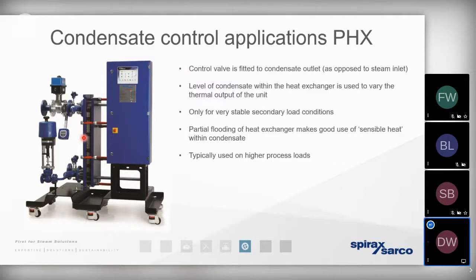The benefit being that regardless of the fall in pressure downstream of the steam trap, we're greatly minimizing, if not eliminating, any flash steam losses or flash steam inefficiencies. So we can actually move the control valve from controlling the steam entering the heat exchanger to controlling the temperature of the condensate leaving the plate pack. It's taking the place of the steam trap, if you like. And in many cases, we can add an extra 2 or 3% efficiency by simply controlling on the condensate side than we can by controlling on the steam side.